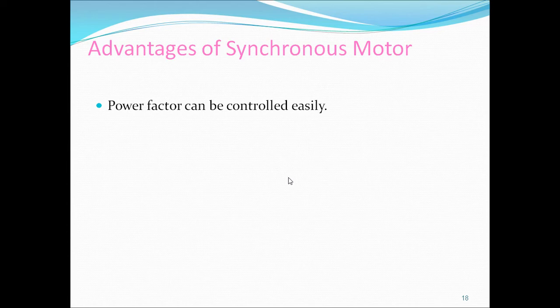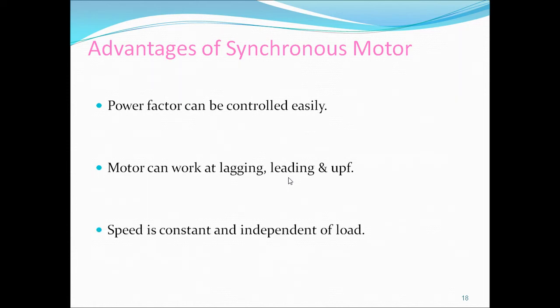By changing the excitation, we can bring it to lagging power factor, leading power factor, and unity power factor. That is the advantage of a synchronous motor. No other motor has an advantage like that, to operate at different power factors: lagging, leading, and unity.